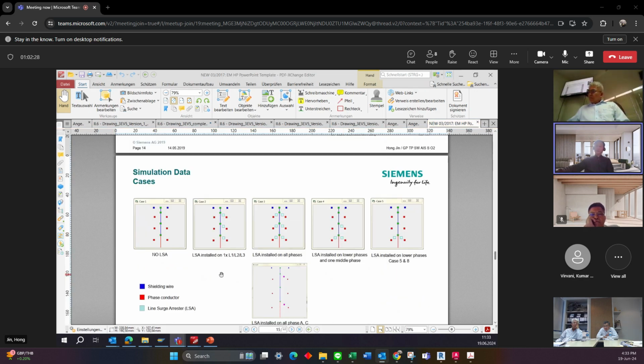So if we come back to the different configurations of EGLA, we have many different scenarios for the line study simulation. Case 4, as we mentioned, is a double circuit transmission line. On the top are 2 shielding wires. And this blue square means the surge arrester. The recommendation is installation on both bottom phases and one of the middle phases. Even better would be installation on the 2 middle phases of both circuits.